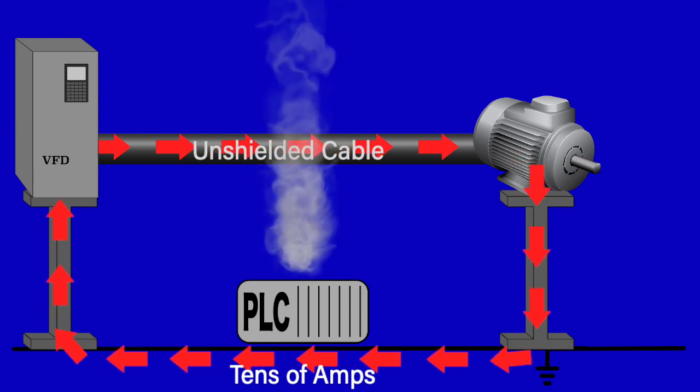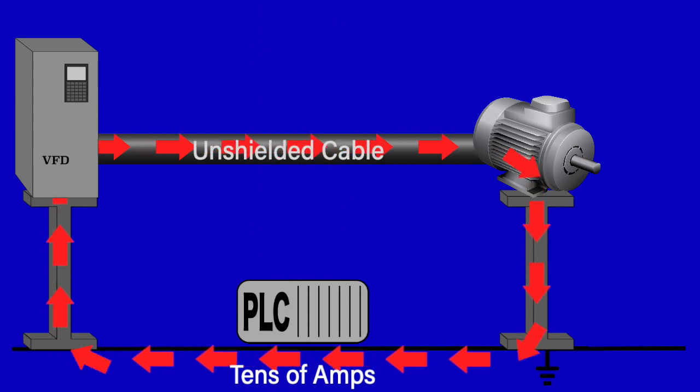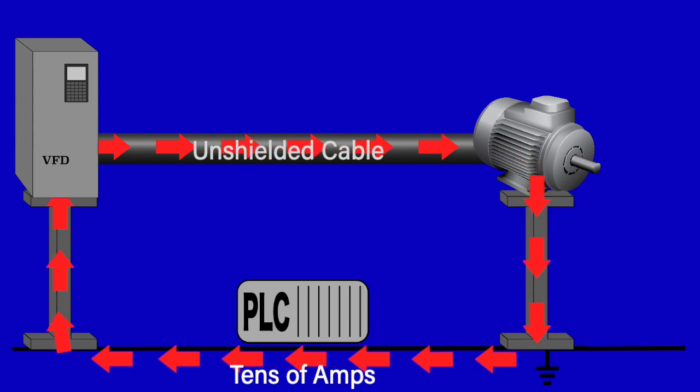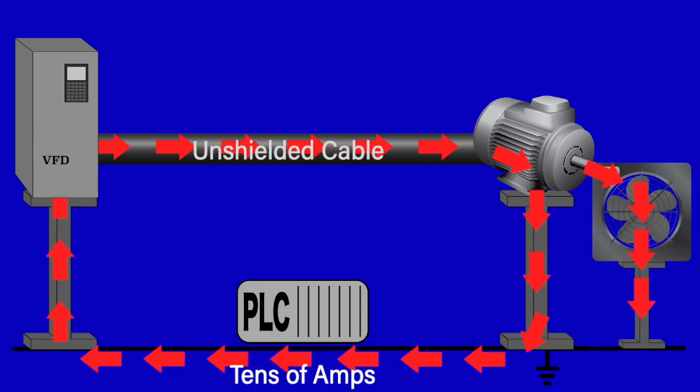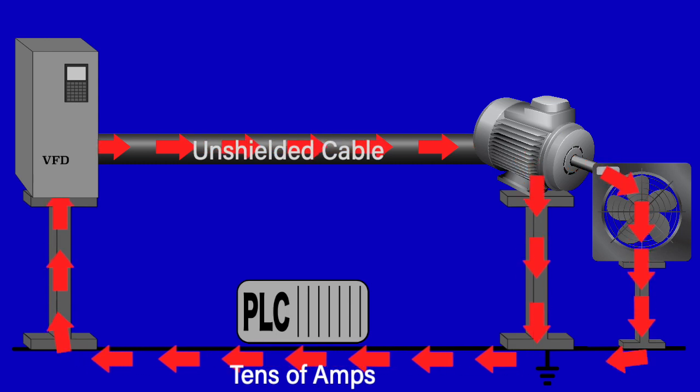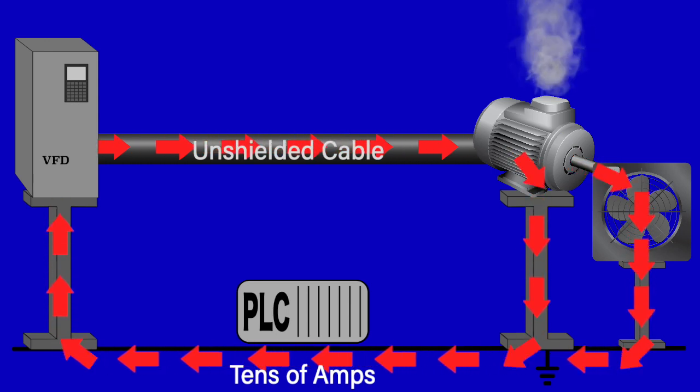Because this current path is unknown, it's impossible to predict where the current might flow on its way back to the inverter. In addition to flowing through the motor frame and base plate to building steel, another possible path is through the motor bearings to the motor shaft, connected machinery, and then to the building steel infrastructure. This path can damage motors by causing bearing damage known as bearing fluting, which can cause motor failure after 3 to 12 months of operation.